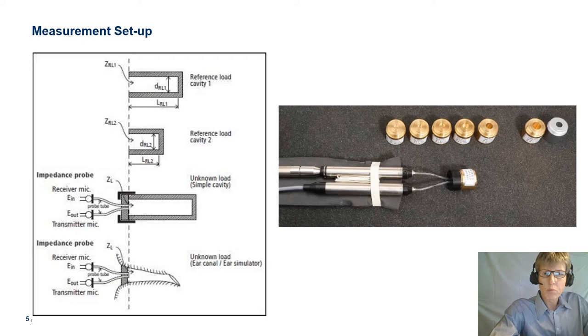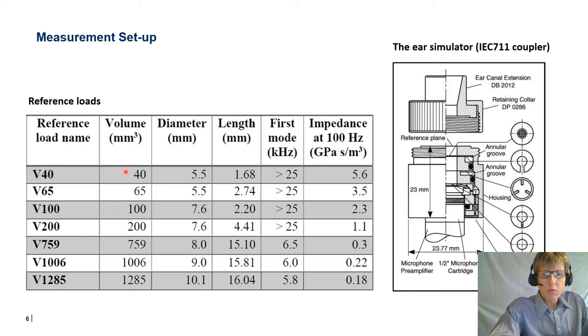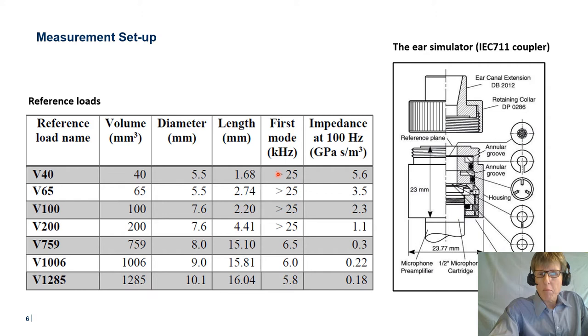Here's an overview of all the reference load cavities used. They range in volume from 40 cubic millimeters to 1285 cubic millimeters. We have the diameter and length listed, as well as the first mode — the frequency where the cavity starts to break up — which occurs above 25 kHz for the small ones and already around 6 kHz for the large ones. At that frequency, the cavity no longer behaves like a compliance. The small cavities have a much higher impedance at 100 Hz than the large ones.